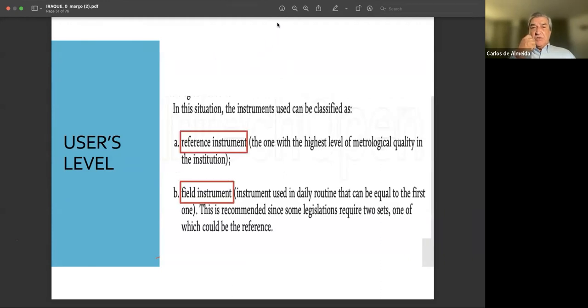In this situation, now at the user's level, which is our level, if you have just one instrument, you have to use it very carefully, because if something goes wrong, you don't have any instrument to measure. But if you have two instruments, which is advisable, we select one as a reference instrument, the one of the two that has the best stability, and the second one is used as a field instrument. They use it on a routine basis. From time to time, you do a cross calibration between the field instrument and the reference instrument.